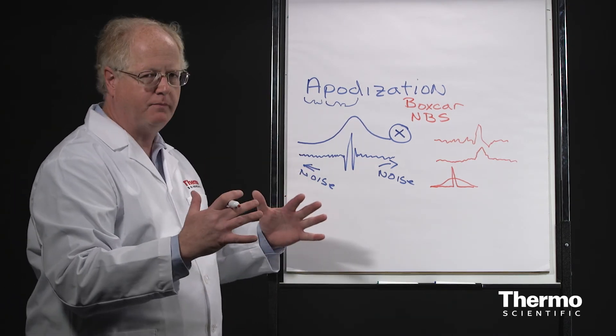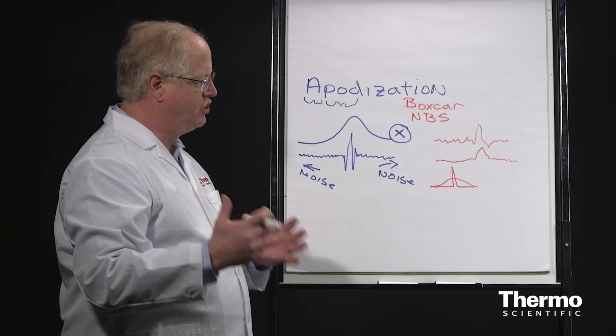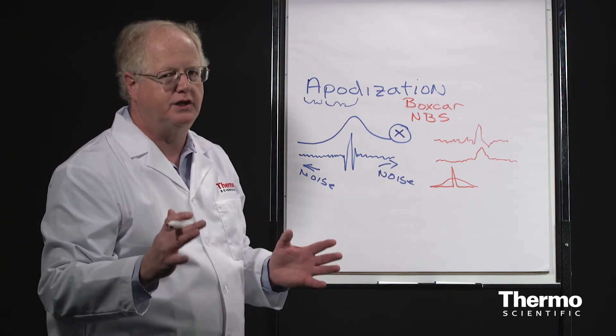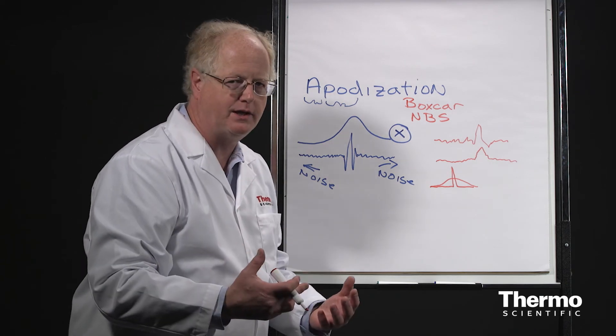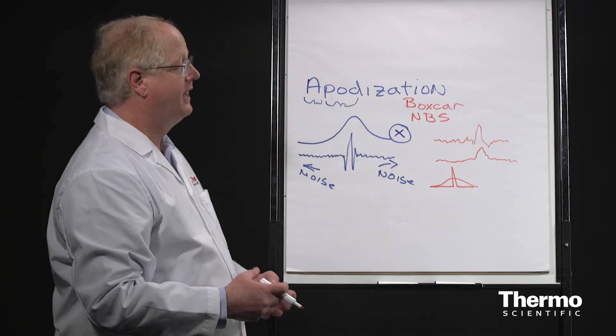If you have a broad spectrum, like a liquid or a solid, generally the apodization function is not going to change the spectrum. In that case, you just use one that suppresses the noise without altering the line width.